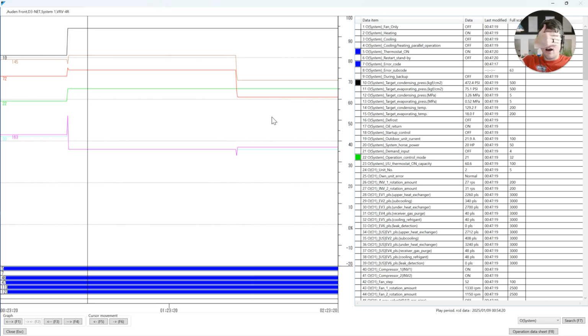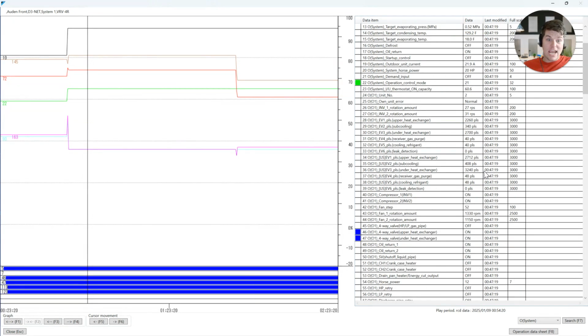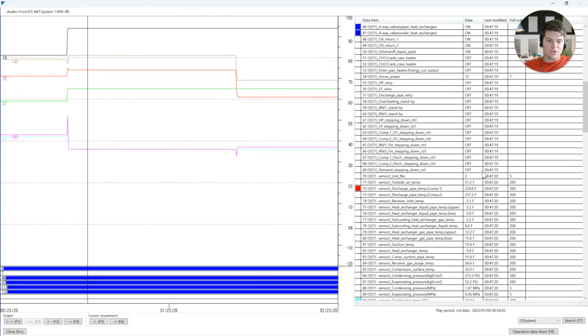And it says, I'm going 120 miles an hour. Let me just close my eyes really quickly to catch some Z's. And it just goes through the roof. So the compressors go, yeah, full speed ahead, right? Full send. And so it's jamming that acceleration to go get that oil back. But the problem is that the discharge superheat is already high. This is only going to cause more damage on the compressor, right? And now it's trying to create that huge amount of head pressure, that large amount of liquid to go through the system. And so let's look at it, right?